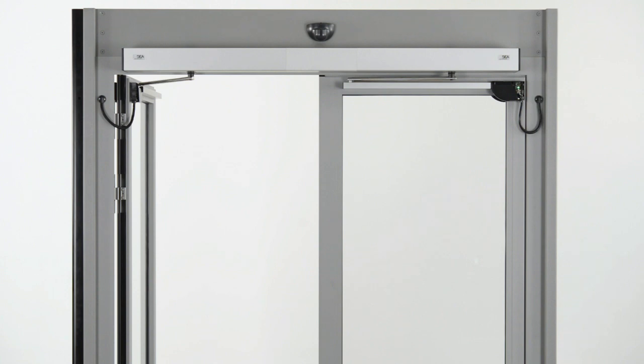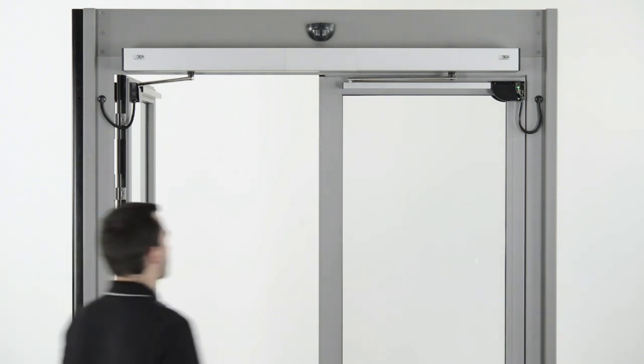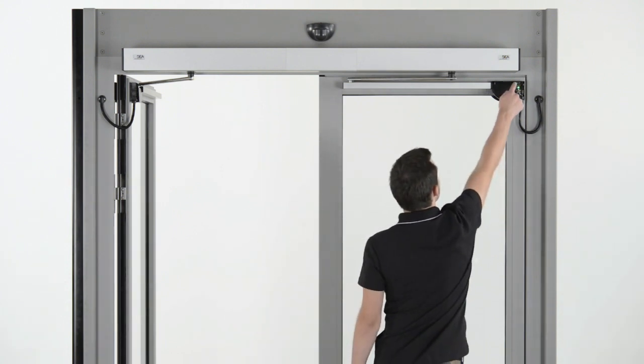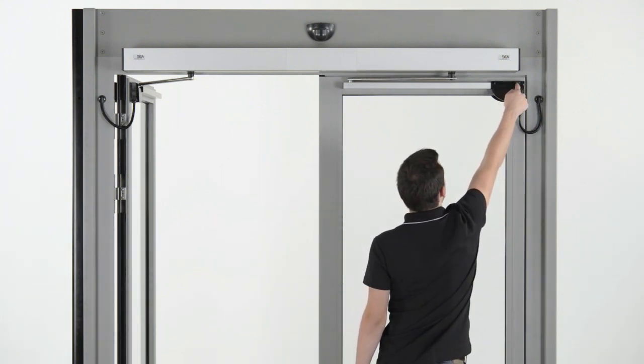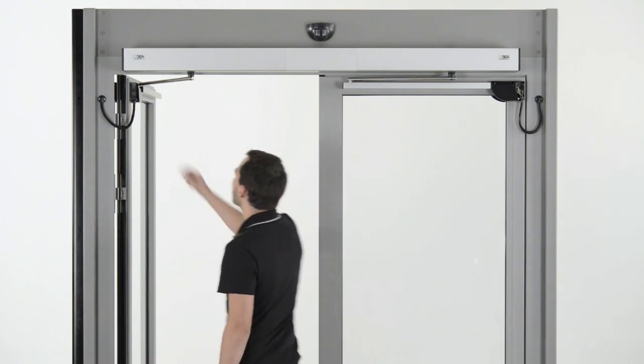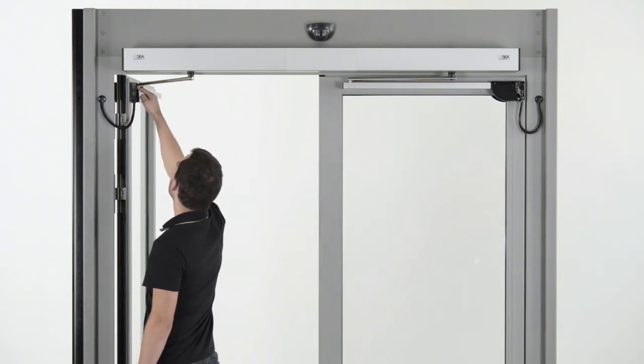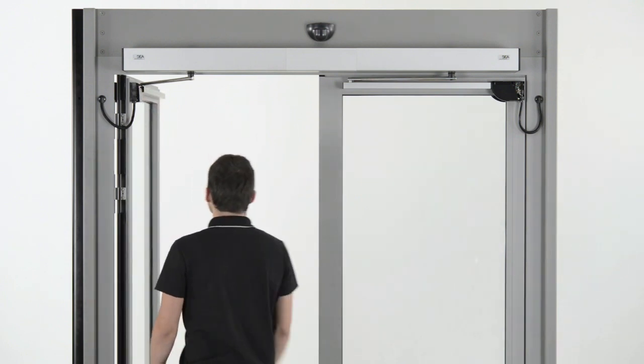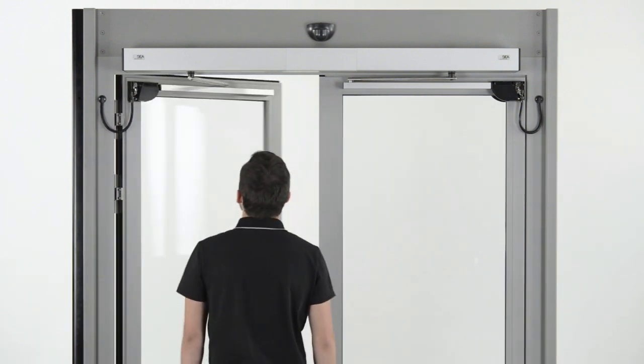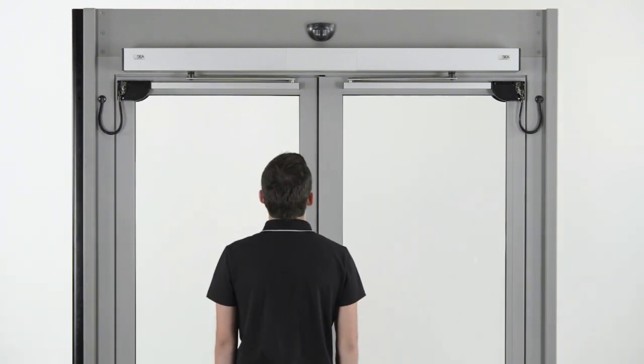Before launching a teach-in, activate the service mode on the master module. Be aware that during the service mode, the safety of the door is deactivated. The service mode can be activated by pressing the push button for more than 3 seconds. It enables the door to close in order to launch a teach-in. The sensor is in service mode when the LED is off.